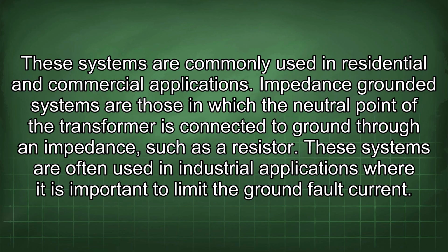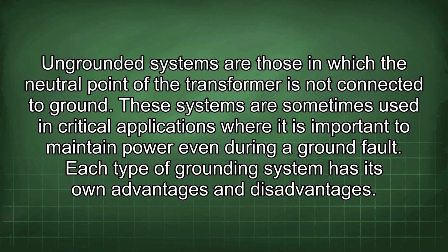Impedance grounded systems are those in which the neutral point of the transformer is connected to ground through an impedance, such as a resistor. These systems are often used in industrial applications where it is important to limit the ground fault current. Ungrounded systems are those in which the neutral point of the transformer is not connected to ground. These systems are sometimes used in critical applications where it is important to maintain power even during a ground fault.